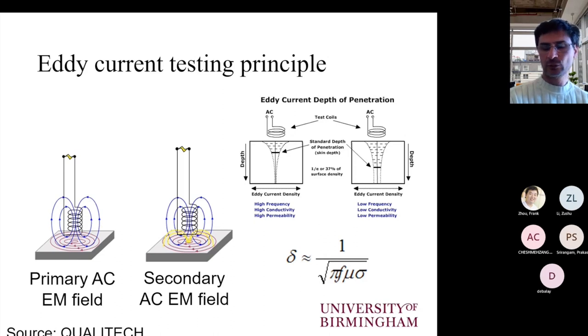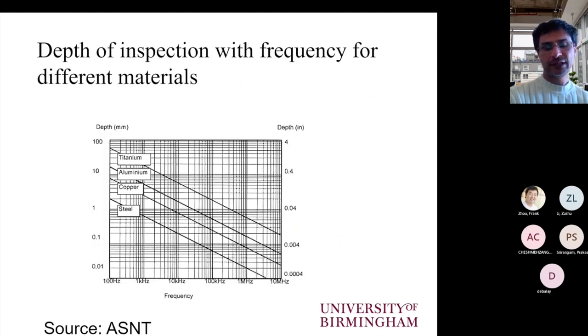In most cases, it will be close to the surface, especially if we are dealing with steel grades which have a high relative permeability. In non-ferrous materials, it is feasible to inspect the entire thickness of the sample, especially in aerospace components which are not thick anyway. But in ferrous materials, it's a different story because the relative magnetic permeability has a very strong effect. And you can see here from this schematic, this plot, what is the relationship between the operational frequency and the depth of inspection in different materials, in titanium, in aluminium, in copper, and steel.